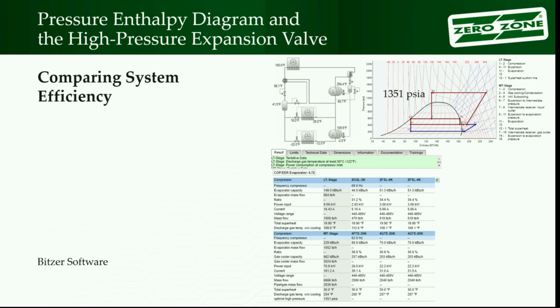The only thing you have to watch out for with the software is that PSIA is in absolute units versus gauge, right? So if you've got nothing better to do in your life, and you keep looking at the Bitzer software and the controller software, you'll wonder why it's always 15 pounds off. One's maybe in PSIA and one's in PSIG.